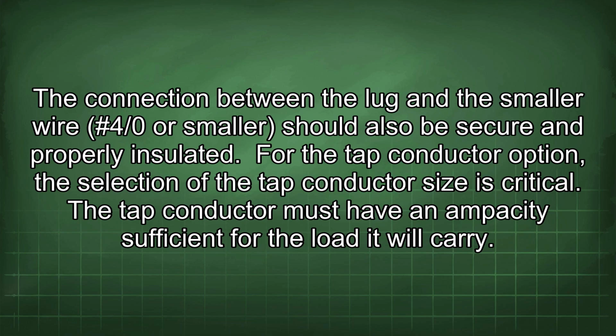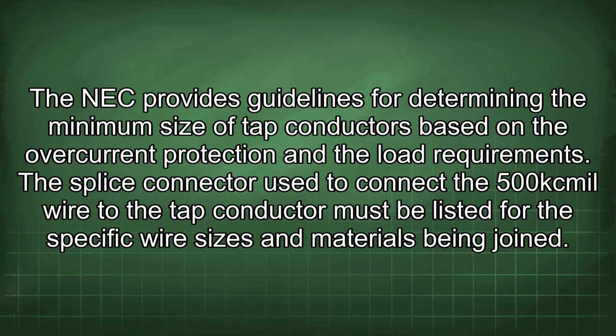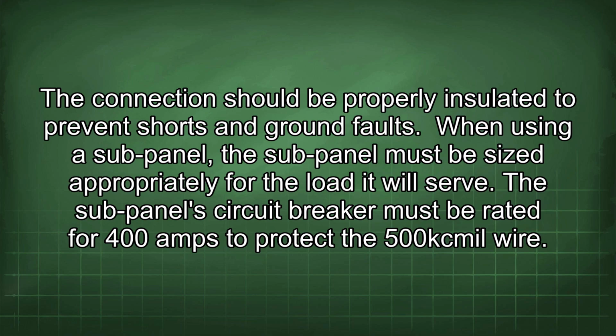For the tap conductor option, the selection of the tap conductor size is critical. The tap conductor must have an ampacity sufficient for the load it will carry. The NEC provides guidelines for determining the minimum size of tap conductors based on the overcurrent protection and the load requirement. The splice connector used to connect the 500 kcmil wire to the tap conductor must be listed for the specific wire sizes and materials being joined. The connection should be properly insulated to prevent shorts and ground faults.